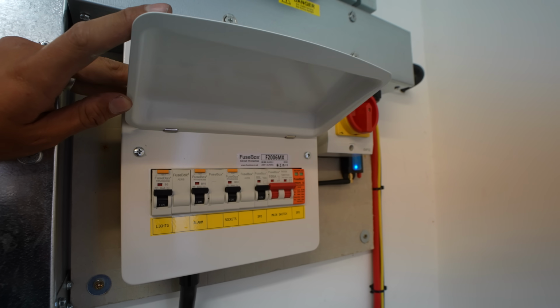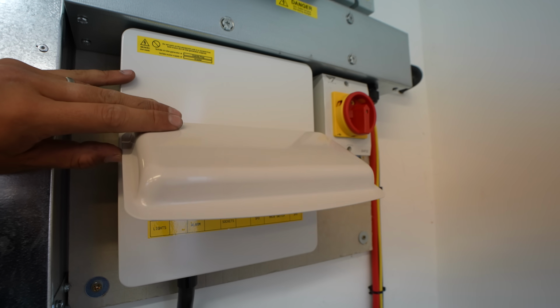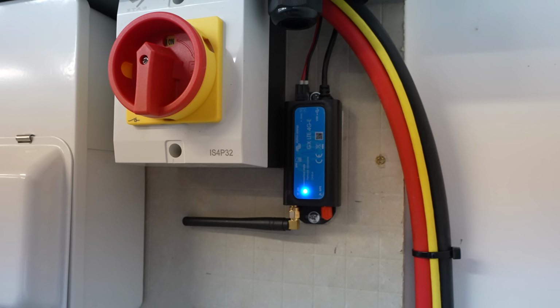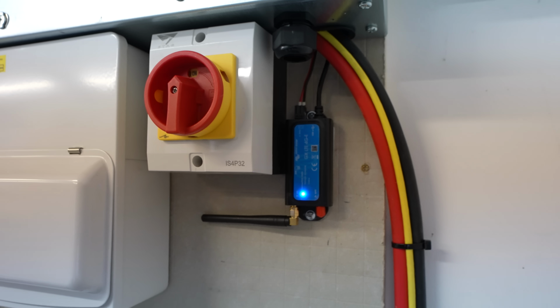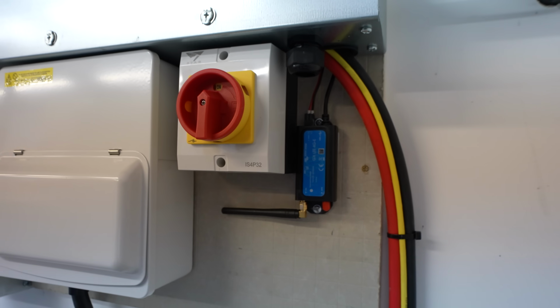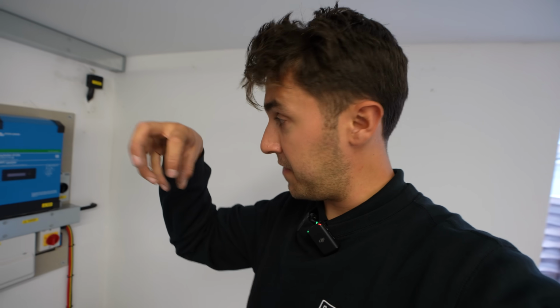In terms of commissioning, there hasn't been tons to do. A lot of this was already commissioned when it was built, but yeah, just making sure that the battery is identified, making sure it knows it's going to be inverting solar, and also making sure it knows that feed out there is a generator input, because we have to use a male plug - you don't want that to ever be live.